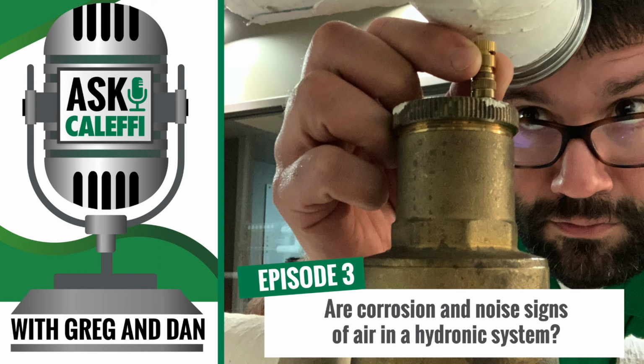It was interesting with that. You look at our smaller coalescing meshes, the glass reinforced coalescing mesh. The edges are really sharp on that unit if you ever pull it out and notice that. That sharpness is there to attract the micro bubbles. They like small, sharp edges. In the fluid, they slow down and they catch everything that's sharp. It'll allow that to rise up and out of the body.